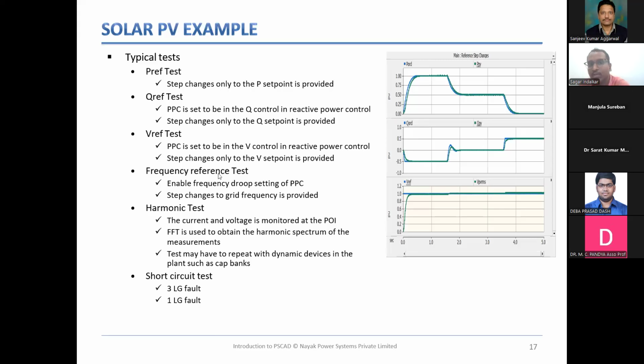So that forms your frequency. Along with that, you also have certain other tests. For example, LVRT, HVRT test, where you create a fault at POI, to check whether the plant stays connected during an LVRT or HVRT event.